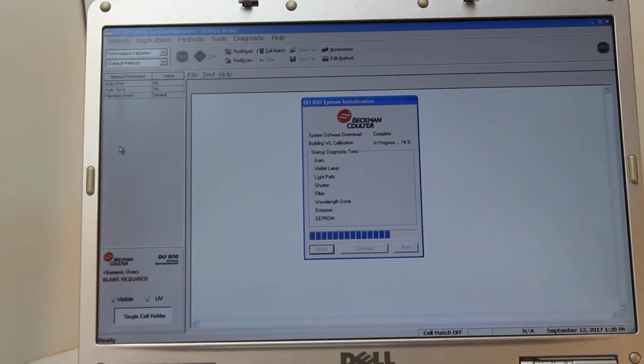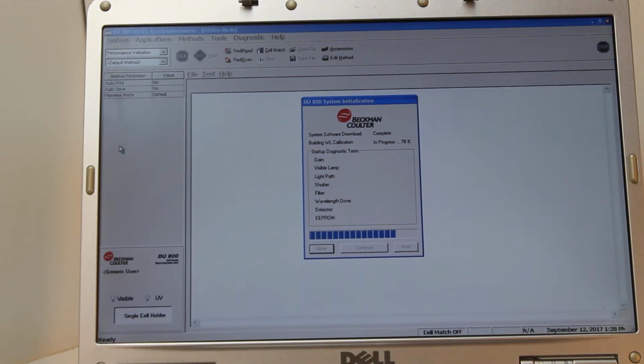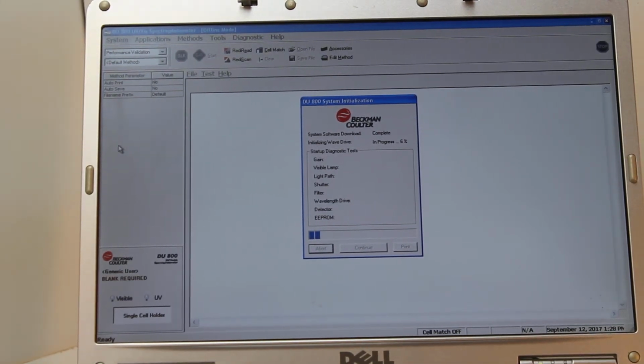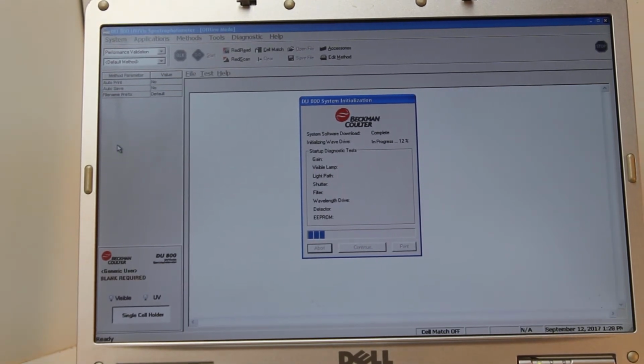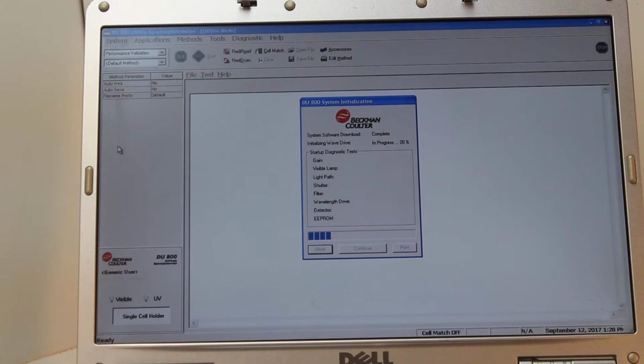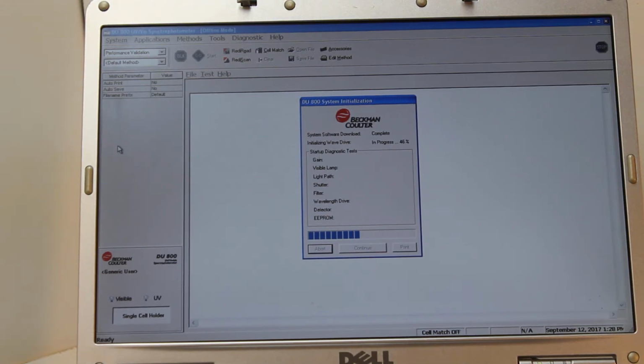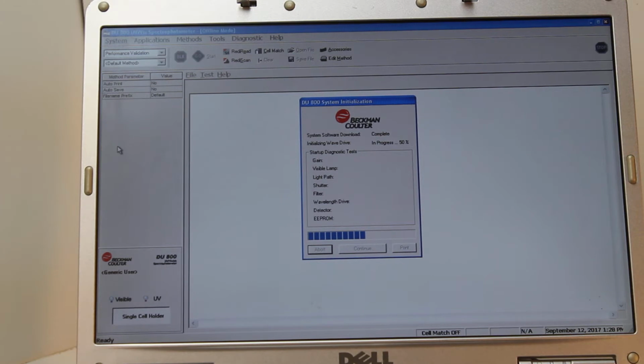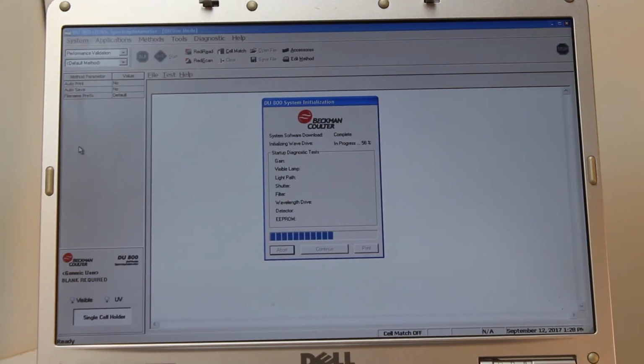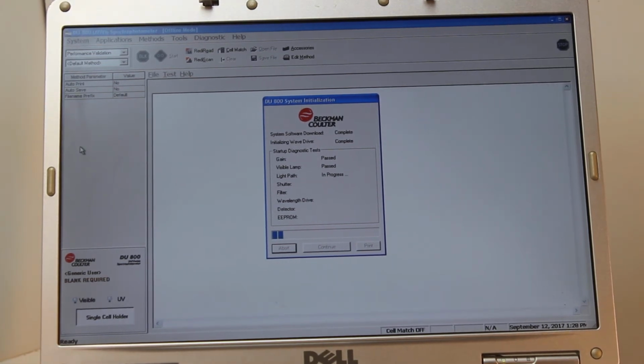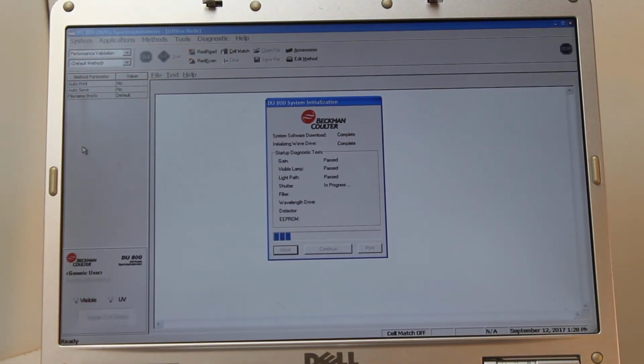And as soon as this is done, it starts checking the monochromator and every optic included in the instrument, starting with the gain, visible light, light path, shutter, filter, wavelength drive, detector, EEPROM, all of them. It's going to check all of them. So you see gain passed, visible lamp passed, light path, everything.